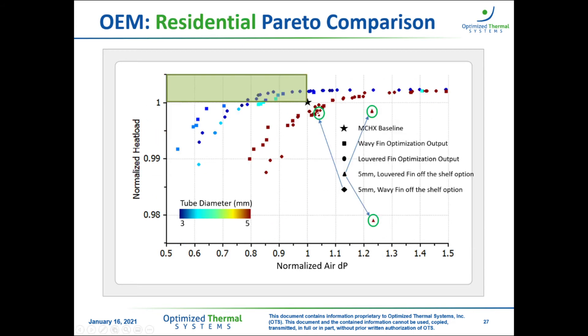For the two-ton residential system, the main takeaway is similar: off-the-shelf fin designs are competitive with the micro channel heat exchanger baseline, and when the fin design is optimized, those designs can actually dominate the micro channel baseline.